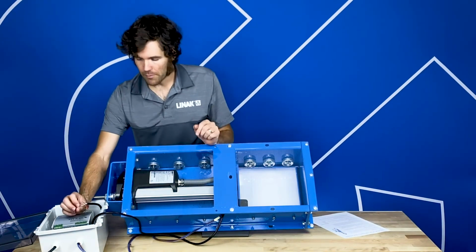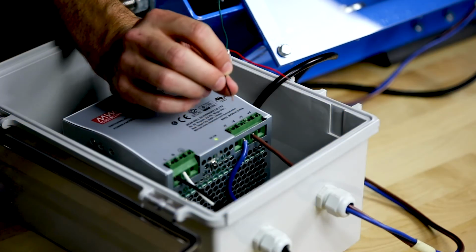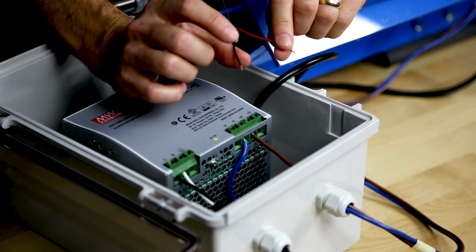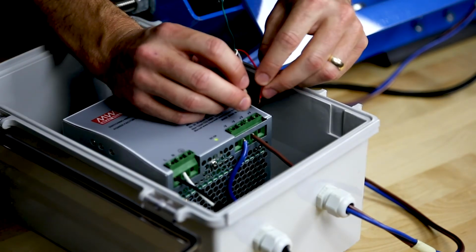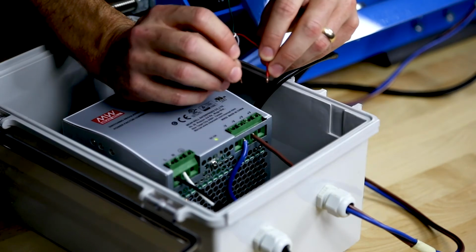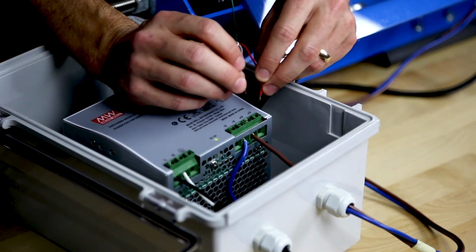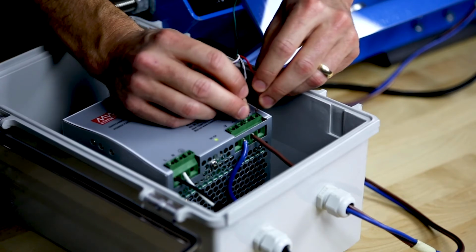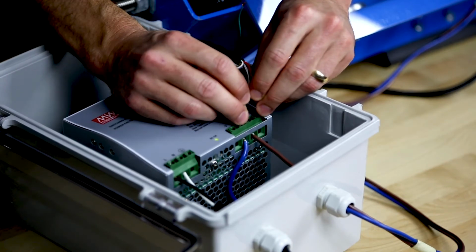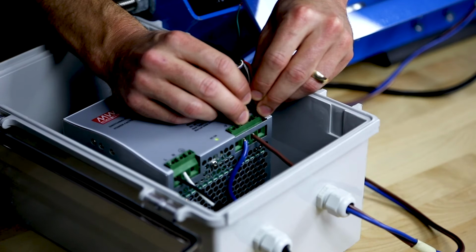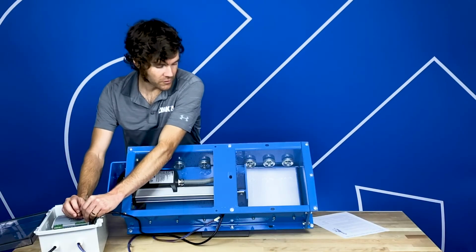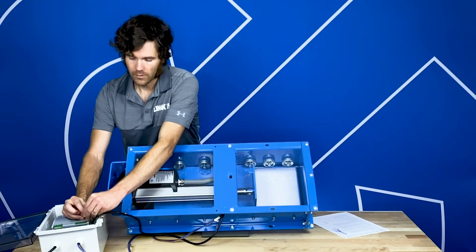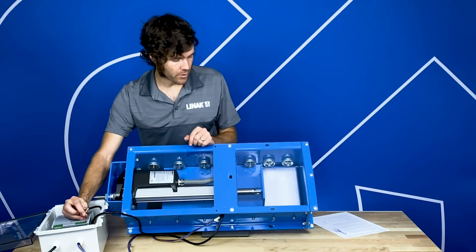Put the actuator in learn mode. The way that you can do that with these wires would be to apply 24 volts to both the red and the black for between 5 to 10 seconds, and then remove both wires and apply the wire for the direction that you want it to do the learn sequence. So 1, 2, 3, 4, 5, 6. Both off and then back on. You'll see that the actuator is running slower than it was before. That's to indicate that you are in fact in learn mode.